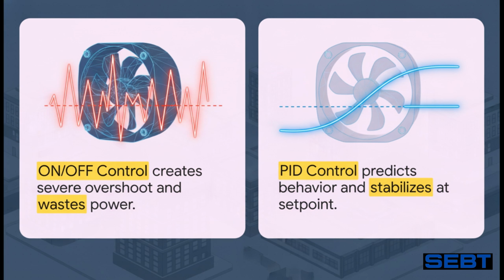Legacy on-off control basically just waits until a room gets way too hot, blasts the AC at 100%, completely overshoots the target, turns off, and then just waits until it gets too hot again. It's this jerky, totally unstable roller coaster that wastes a massive amount of fan power. But look on the right.